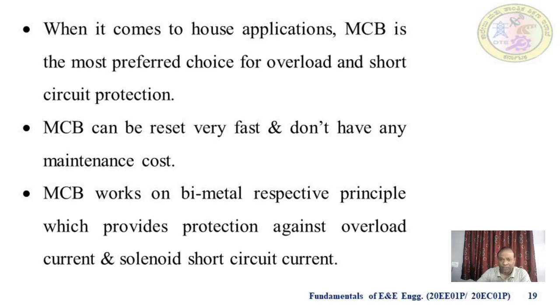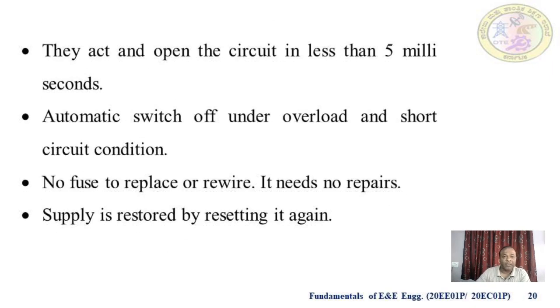The MCB works on a bimetallic strip principle which provides protection against overcurrent, overload current and short circuit current. It can open the circuit in less than 5 milliseconds. It automatically switches off under overload and short circuit conditions. No fuse needs to be replaced or rewired, it needs no repairs, and supply is restored by simply resetting it.